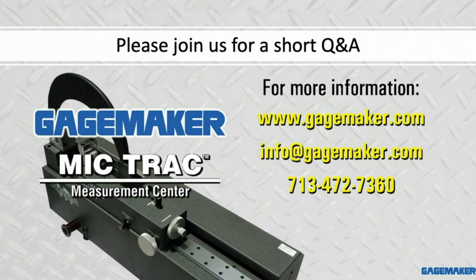If you're measuring parts or calibrating some hand tools that don't require the extreme accuracies of the unit, it can absolutely be on the shop floor. And nothing is going to happen to a Mic Trac on the shop floor. It's built to be in different conditions, but if you're calibrating an instrument or measuring a part, you want the temperature of that component to be as close to the temperature of the Mic Trac as possible, because we all know things expand and contract with temperature changes. So if they're dissimilar materials, basically you want them at the same temperature when measuring.